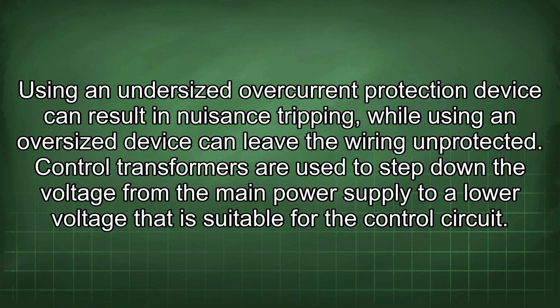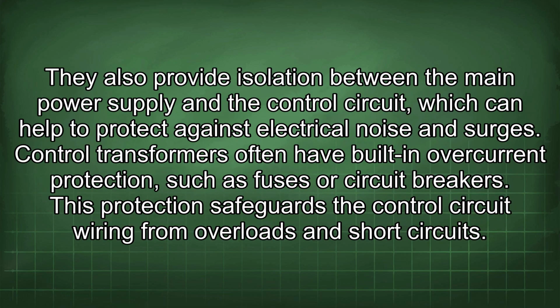Control transformers are used to step down the voltage from the main power supply to a low voltage that is suitable for the control circuit. They also provide isolation between the main power supply and the control circuit, which can help to protect against electrical noise and surges. Control transformers often have built-in overcurrent protection, such as fuses or circuit breakers. This protection safeguards the control circuit wiring from overloads and short circuits.